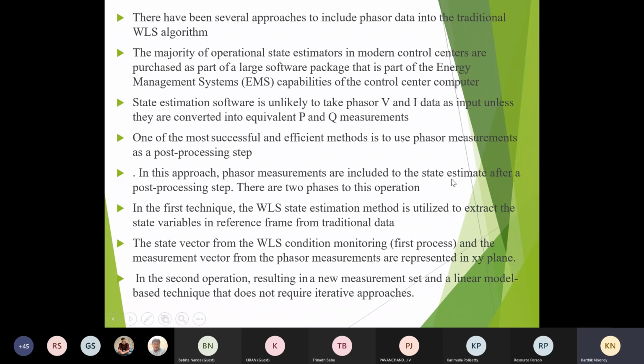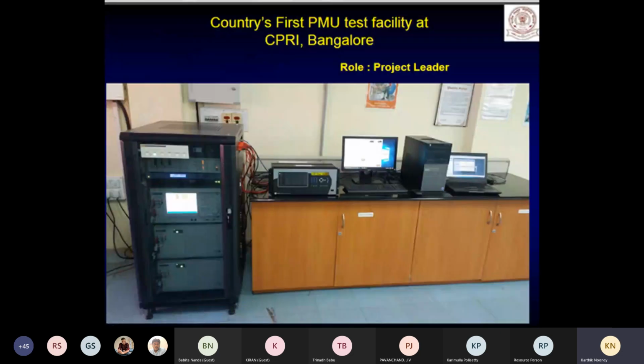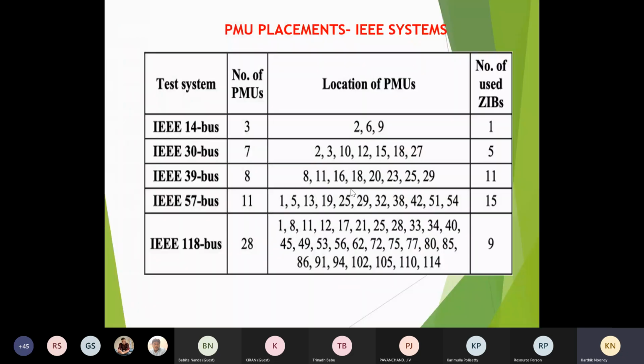So in this approach, phasor measurements are included after a post-processing step. See, in the first technique, what I have said, the weighted least square approximation method is used to extract state variables, and the state vector from the weighted least square approximation measurement vector is represented in the XY plane. In the second operation, resulting in a new measurement, a linear model based technique that doesn't require any iterative approach is considered. This is the country's first PMU at CPRI Bangalore. Some diagram I have gathered from the net. And this is, according to IEEE systems, how many PMUs we have to use for the 14 to 30 bus system and the number of channels where exactly they are using.